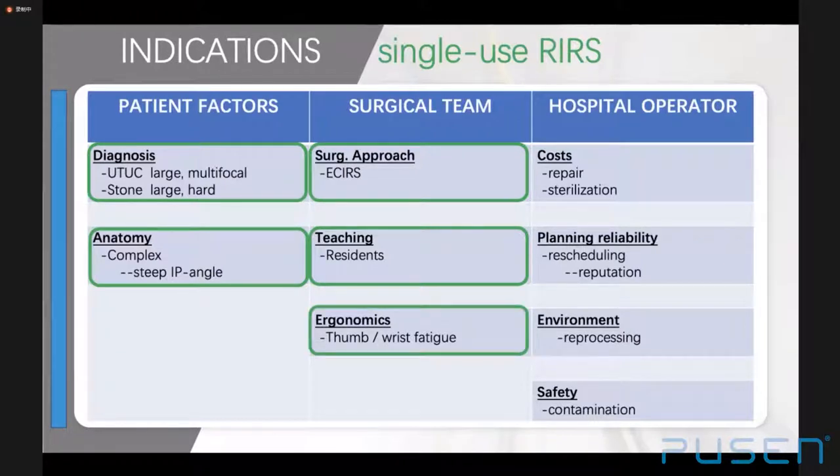For nursing staff, it is convenient to open a single-use scope and dispose of it directly after the procedure. For surgeons, the median thumb/wrist fatigue scores tend to be better with single-use scopes compared to standard reusable ureteroscopes, especially in long-lasting procedures with lightweight scopes — the PUSEN weighs just 91 grams. Hospital departments may find single-use scopes more suitable for low-volume centers; however, decisions must be individualized for any institution based on case volume, repair costs, sterilization, staff, and purchase prices.